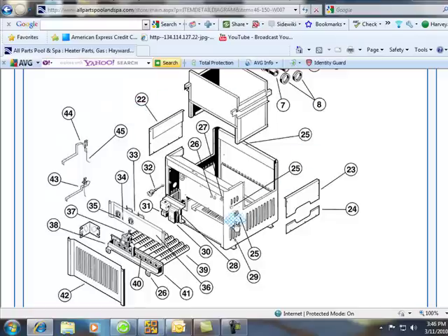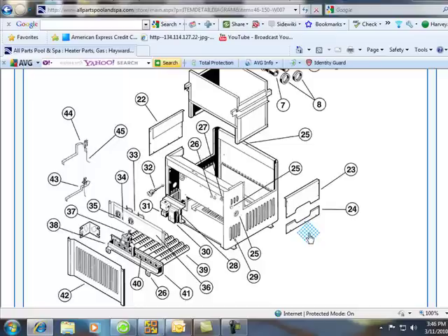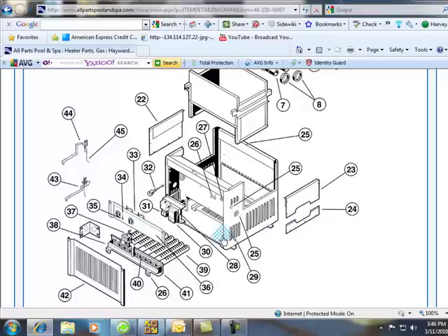And on a millivolt, I can't drill it in enough. Well, the meter is showing 0.666 ohms. It's good, but it's not really good. On a millivolt system, it has to show up as a dead short. Bing. It whistles at you. It beeps at you. It shows you complete zeros.